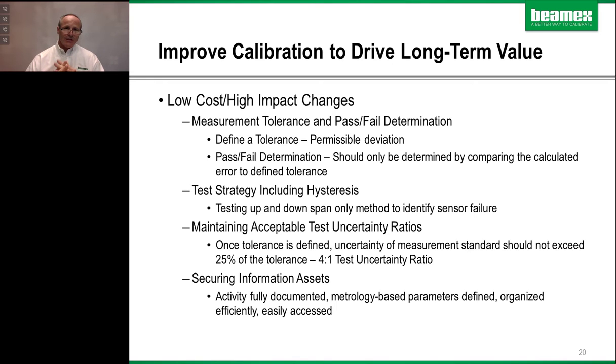Each measurement has a test uncertainty ratio, but we make it real easy. Typically, the industry standard is, let's look at the test uncertainty stated by the measurement standard. So your calibrator has an accuracy statement, and we can use that. That accuracy cannot be more than 25% of the measurement we're trying to make, which gives us a 4-to-1 test uncertainty ratio.